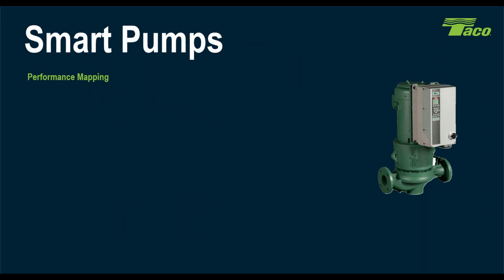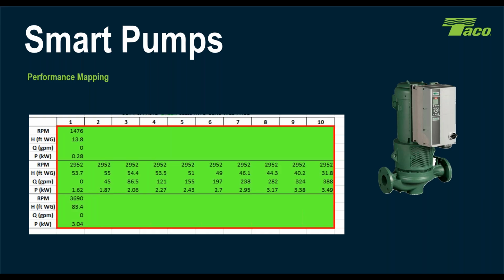So then we take that data, and we can't just dump a pump curve into the pump exactly. It goes into what essentially looks like an Excel file. This is half of the plot. We actually plot 20 points, so we know 20 different spots on the curve. And we take those numbers and plot them into what essentially looks like an XY lookup table, if you're familiar with Excel. That's kind of what it looks like. And that gives us the performance map for that entire pump over its entire operating range.